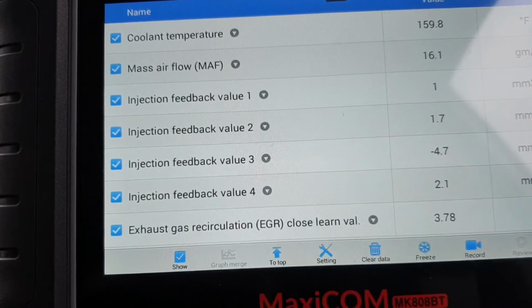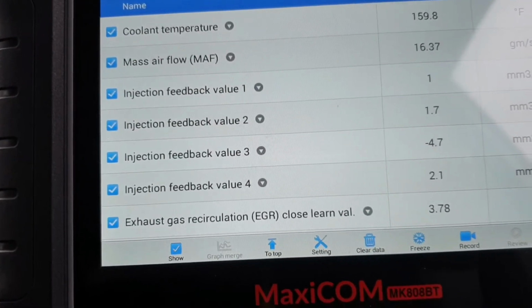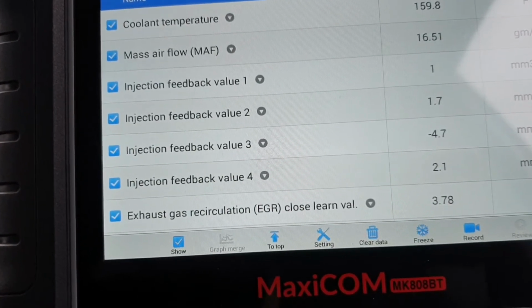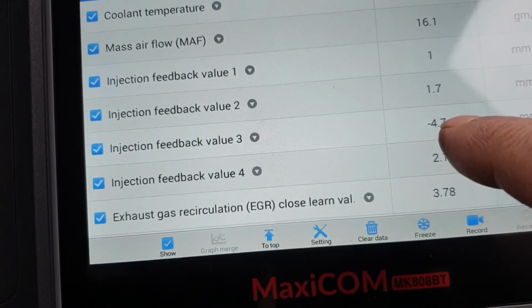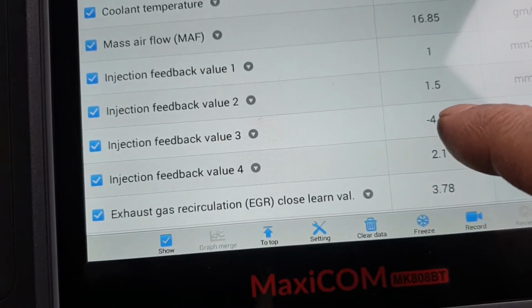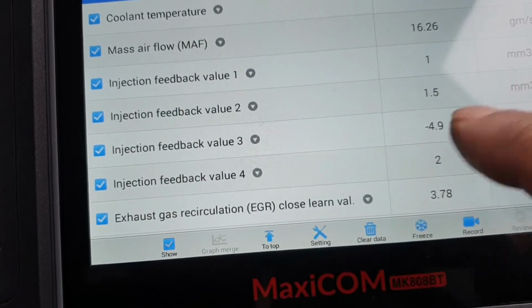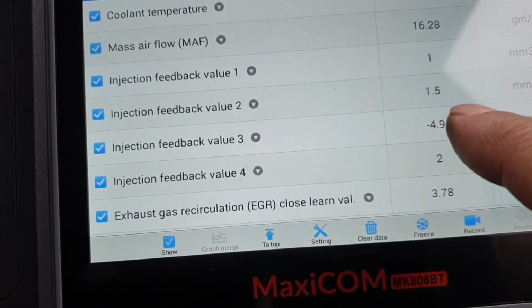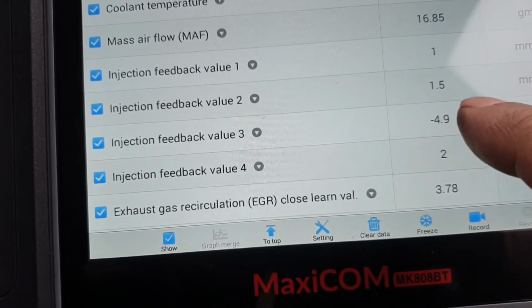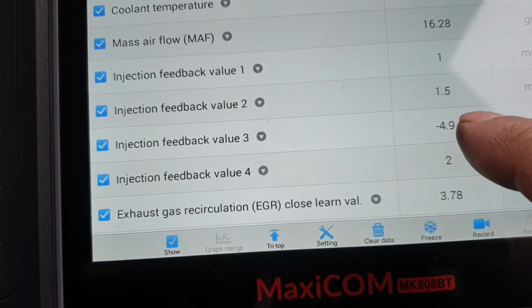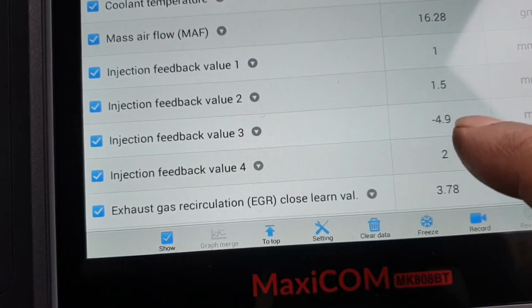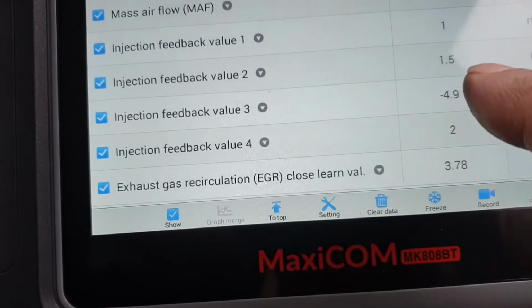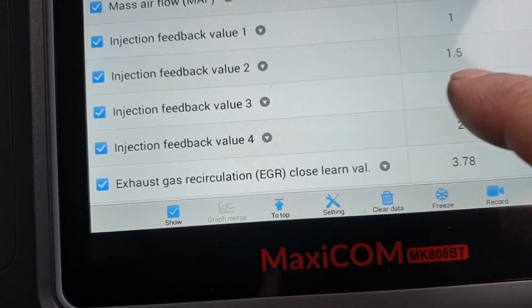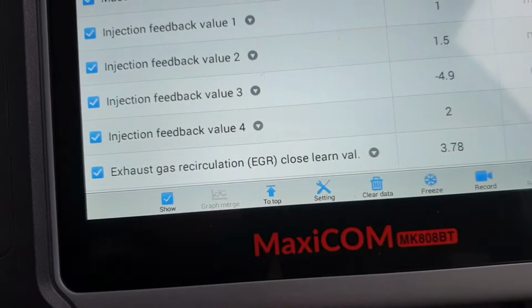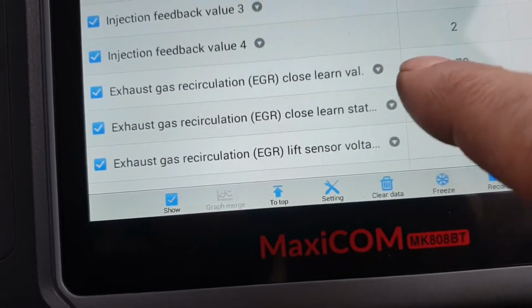Injector feedback value 2 is 1.7. Injector feedback value 3 is this one. So right now it's minus 4.7. So if this one reaches even minus or plus 5, that is no good for the injection. The manufacturer specification is between minus 3 to plus 3. So this is the injection feedback value for injector number 3. Injector 4 is good, no problem.